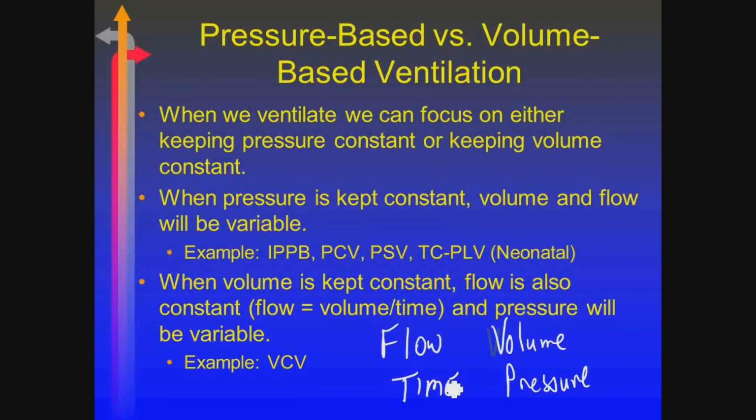Other end of the spectrum, let's keep volume constant. A volume-based breath. In a volume-based breath, the volume is going to be the same each and every breath, regardless of the resistance or compliance. What's going to be the variable in that case? Pressure. You guys probably saw that when you were delivering your IPPB, a pressure-based breath. You change the amount of pressure, you change the tidal volume delivered. I don't know if they manipulated the compliance and resistance of the lungs, but that'll do the same thing. Okay.